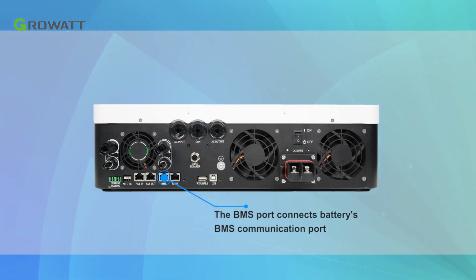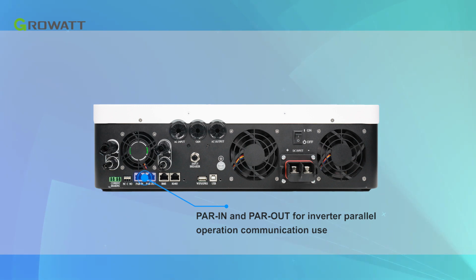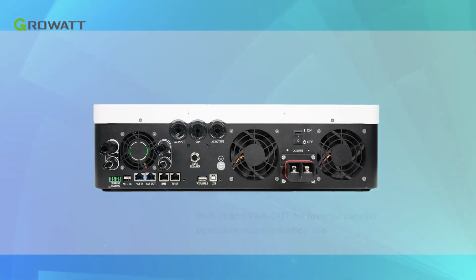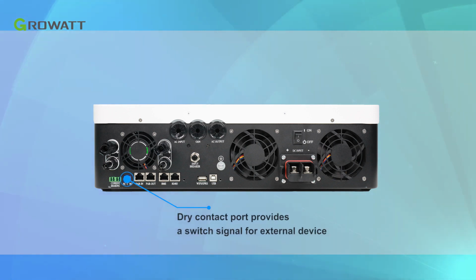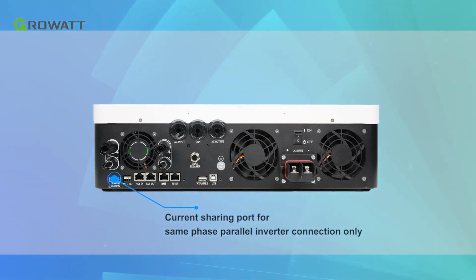The BMS port connects to the battery's BMS communication port. Parallel in and parallel out ports are for inverter parallel operation communication use. The dry contact port provides a switch signal for external devices. The current sharing port is for same-phase parallel inverter connection only.